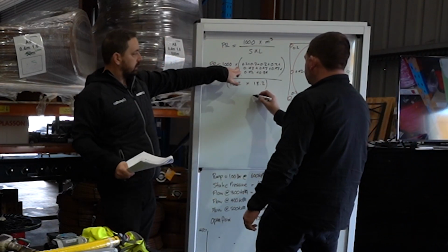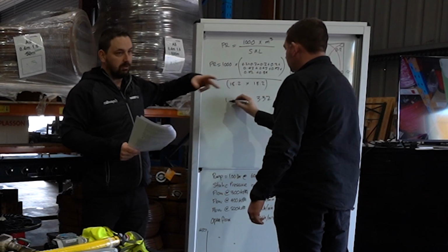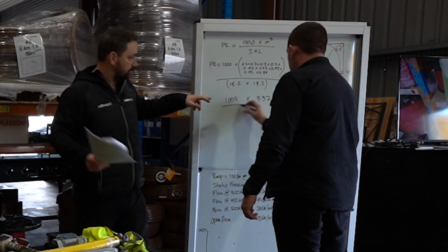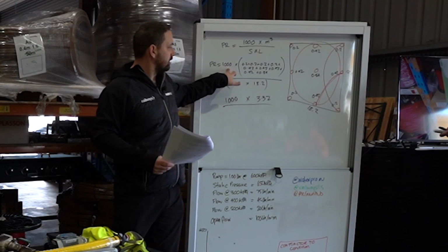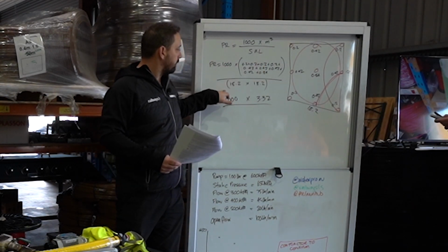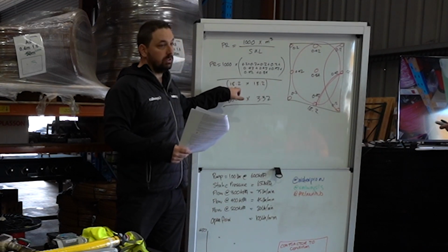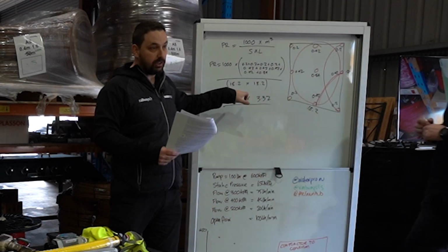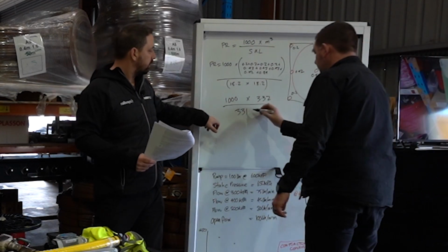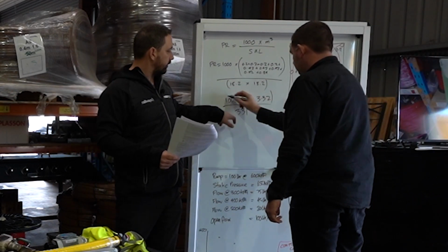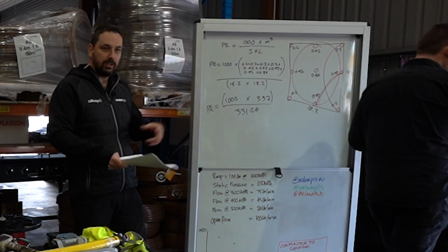So what Clint's done here is the same process that we do, just we've got spreadsheets that we've tried to automate this with, but we add it all together. The formula is 1,000 times the total of that divided by the spacings of the sprinklers. Sorry, for this area, it's the area length and width, which is 1,000 times 3.32 divided by 331.24. Does that make sense, that math? We're just adding this data up to get a total area.